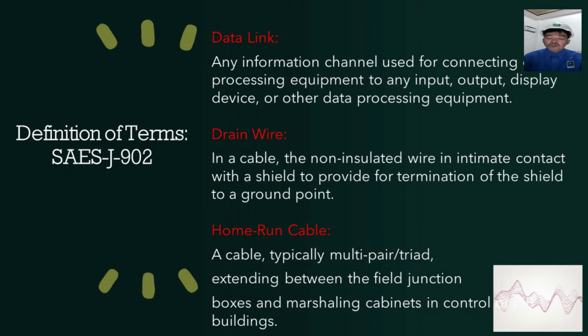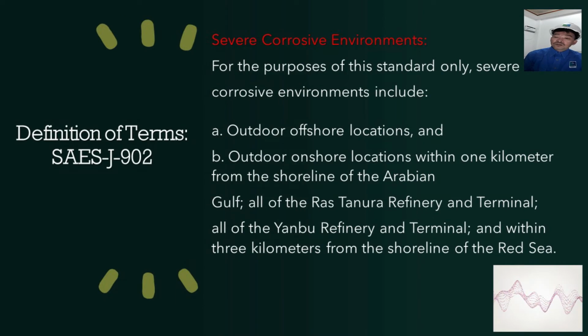We have the home run cable. A cable, typically multi-paired or triad, extending between the field junction boxes and marshalling cabinets in a control building. These are the main cables normally found installed in a home run cable. We have a definition for severe corrosive environments.